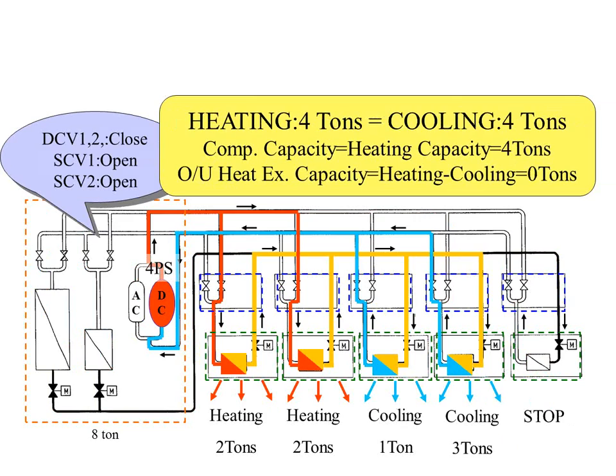And then, of course, if the heating and cooling zones ever matched up perfectly, which is very rare, obviously, then I would shut off all the coils in the outdoor unit, and I would reject nothing outside and take nothing from outside. I would just have 4 tons of heating grabbing their heat from the 4 tons of cooling zones, and my compressor would basically be like a circulating pump, right? And that would be a super efficient scenario.